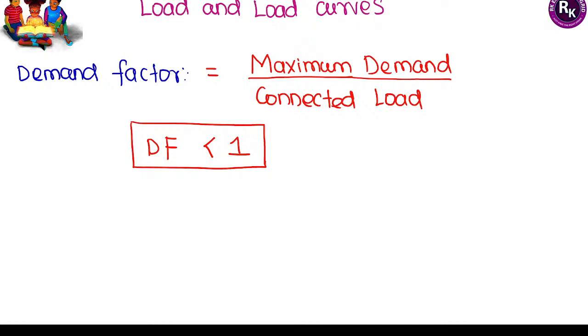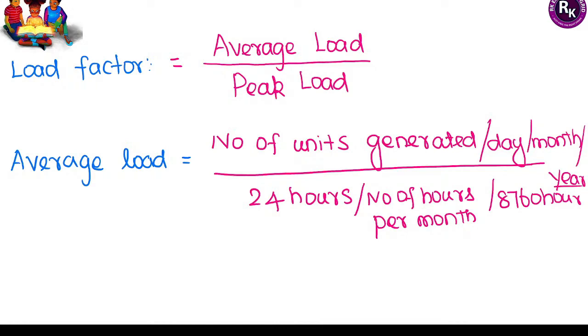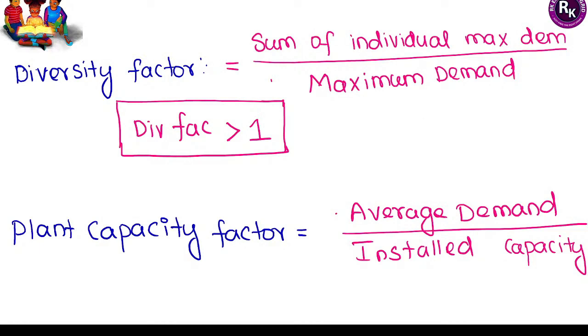Other important factors for effective power transmission: demand factor is the ratio between maximum demand and connected load, and should always be less than one. Load factor is the ratio between average load and peak load. Average load is total units generated divided by the time period — 24 hours per day, total hours per month, or approximately 8760 hours per year depending on the period considered.